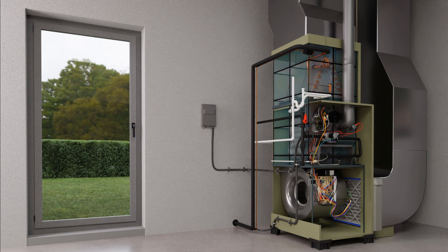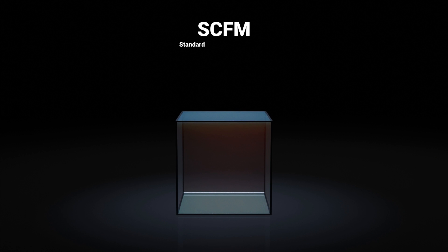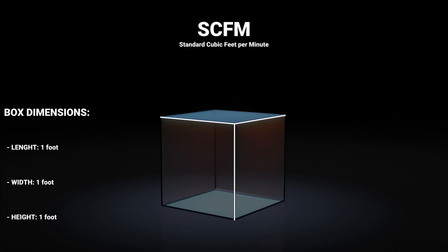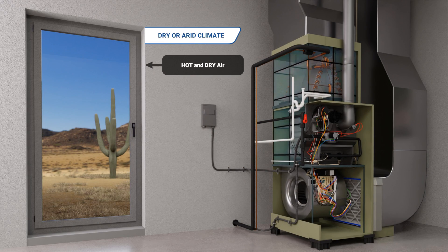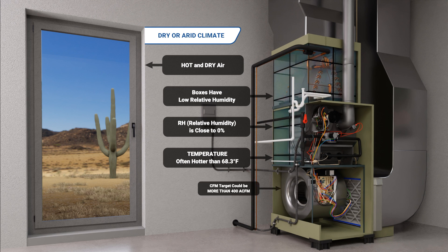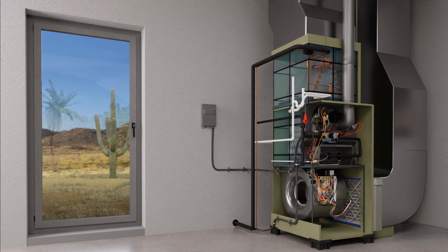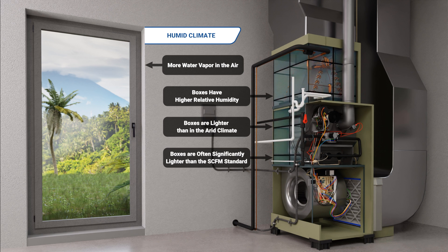Even in a case where someone is shooting for a CFM target of 400, the actual cubic feet per minute, or ACFM, may need to differ slightly because the air may be heavier or lighter than the standard SCFM. SCFM refers to the CFM of a 1-foot by 1-foot by 1-foot box of air at 68.3 degrees Fahrenheit and 0% relative humidity. In a dry or arid climate where we have hot, dry air, those boxes of air will have a low relative humidity, close to the 0% RH of SCFM, but they will often be hotter than 68.3 degrees, so you really could have a target of more than 400 ACFM. In humid climates, the air will contain a lot more water vapor — and because water vapor is lighter than nitrogen and oxygen, these boxes of air will be lighter than in the arid climate and significantly lighter than the SCFM standard in many cases.